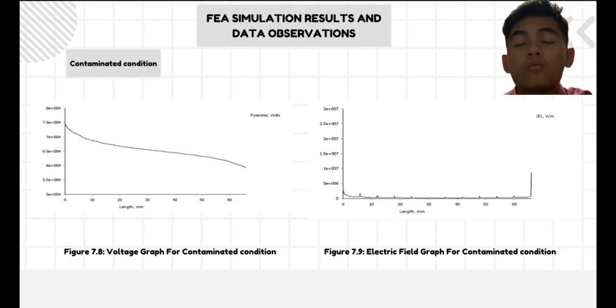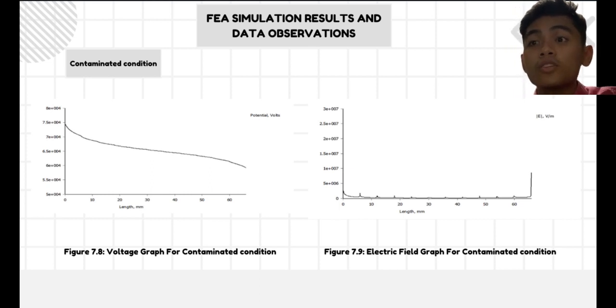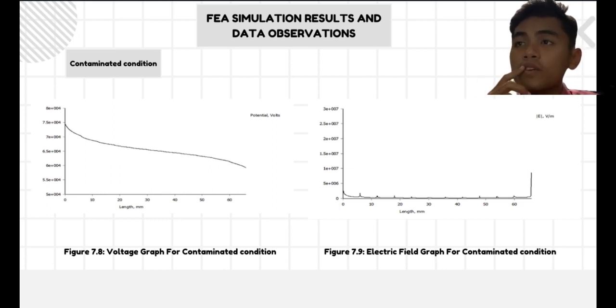Okay, for the next, I will explain the contaminated condition for the voltage graph and electric field graph. For the voltage graph, you can see figure 7.8 illustrates a graph showing the relationship between length and voltage for a contaminant condition. The graph shows that as the length of the insulator increases, the voltage slowly decreases. The contaminant can create conductive paths allowing current to flow through the insulator, which is undesirable. When a current flows through the insulator, it can lead to leakage current and a reduction in the insulation performance of the insulator.